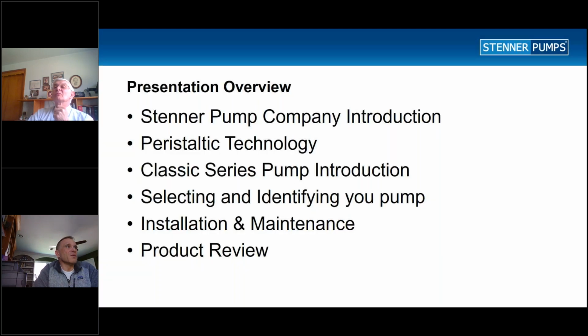What we're going to do is go through a company overview on the Stenner Pump Company peristaltic technology. We're going to go through our classic pump and discuss some different service items that come up most commonly on the classic. We're also going to review how to select, identify pumps, and how to size them properly. As far as wear on pumps, sizing tends to be the biggest culprit for undue wear on a pump. We're going to go through some installation and maintenance. I'm also going to cover some different things that I see in the field and different things that you could do to help maintain the pumps. And then we're going to go through a product review.